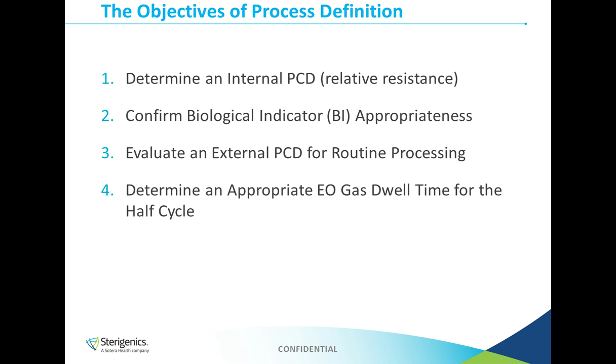First, we're going to talk about determining an internal PCD. You may be asking, so what is a process challenge device, or a PCD? You're going to hear that a lot. It is a device that's inoculated with a biological indicator. This could be a BI disc, a BI spore, or even liquid inoculum. And the BI is placed in the most challenging to sterilize location in this device. And this is to evaluate the delivered lethality of those process parameters. Where you decide to put that BI needs to be documented, both where you place it and the rationale for why you're placing it there.